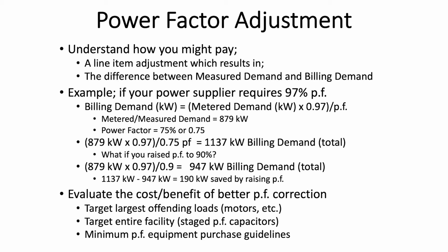So my billing demand that I pay for is my metered demand, the kilowatts that I set, times 0.97 divided by the power factor at my facility. So 879 times the 0.97, let's say my power factor was 75%. I have a really bad power factor. I divide by the 0.75 and I get 1137 kilowatts of billing demand. So now I set 879, but I'm paying for 1137 with the power factor adjustment.